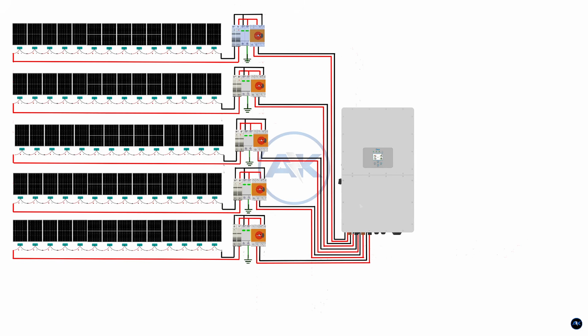Now we connect the strings to the MPPTs. This 40 kilowatt hybrid inverter has 4 MPPTs, and each MPPT can accept 2 strings. We are using 5 strings total. Connect string 1 and string 2 to MPPT 1 using the 2 available DC input ports. Connect string 3 and string 4 to MPPT 2. Connect string 5 to MPPT 3. MPPT 4 will remain unused.